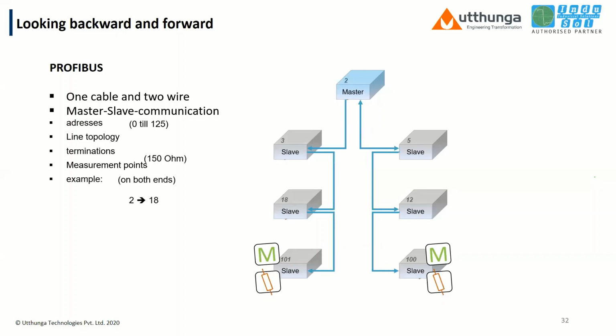Here you can see how the data is transmitting. So we will just take a case here. Slave 3 is having an issue. Just think this is a real plant case. Slave 3 is having an issue, and we don't know what the exact issue is. It may be due to electromagnetic interference, or cable issues, or an impedance issue. What will happen? There will be a lot of reflections if there is an EMI issue or any impedance issue. Here it will be a lot of reflections.